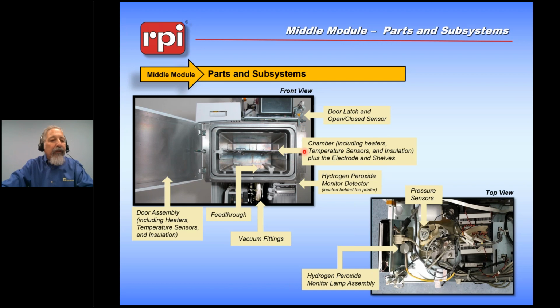We also have a door sensor. This door sensor makes sure that you cannot turn the low frequency power supply or the plasma on while the door is open under any circumstance. Also within the door frame, we have heaters to prevent the hydrogen peroxide from condensing on the inside of the door. We have a monitoring system for the hydrogen peroxide, which starts at the top of the chamber with a UV lamp that sends light through 3 separate lenses, one that's mounted here at the top of the chamber, one that's mounted here at the bottom of the chamber, and one that's mounted right above something called the hydrogen peroxide monitoring detector, which is screwed into the bottom behind the printer.